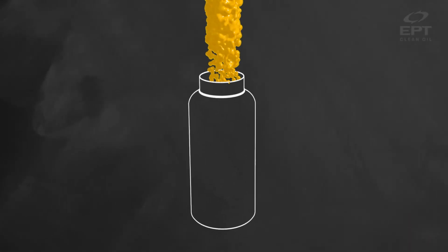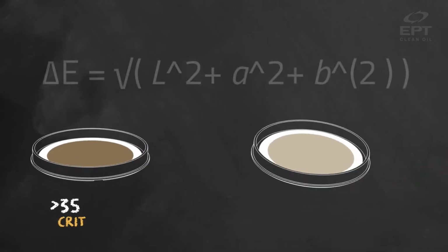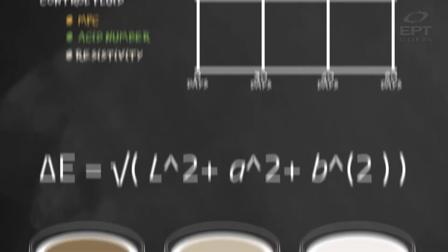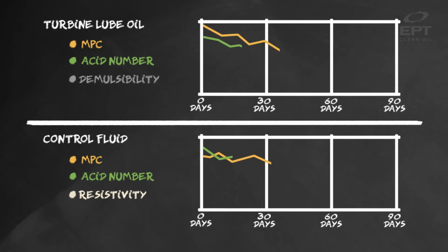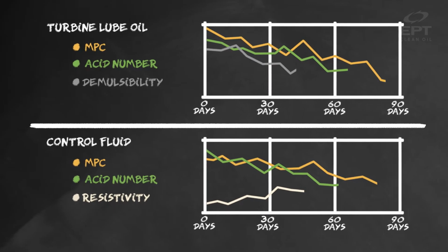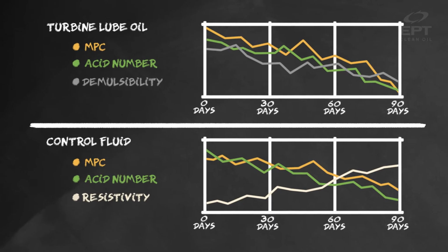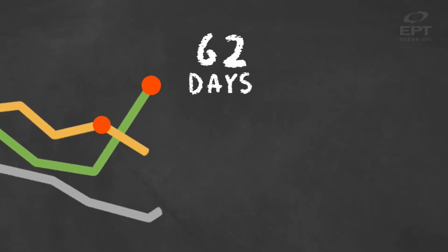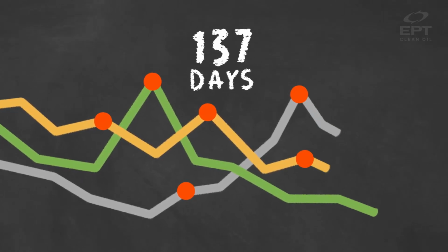Before installing new ICB filters, take a fluid sample. The resulting analysis will be compared against the pre-install sample. The trend we want to see is continuous progress in fluid quality with decreasing MPC, patch weight, acid number, as well as many other vital fluid parameters. Hiccups in the trend are data points that indicate your filter change interval may need to be decreased to keep the trend line moving in the right direction.